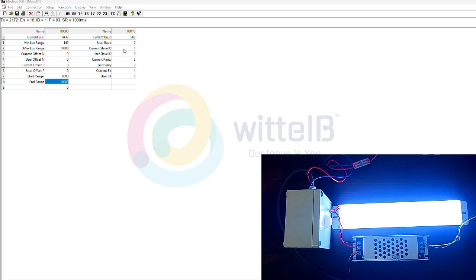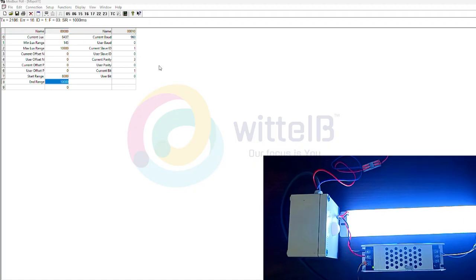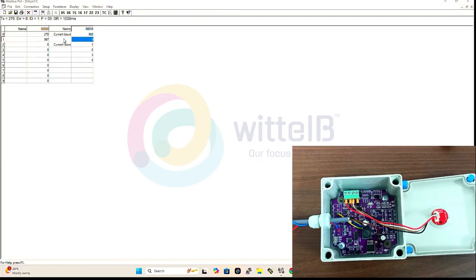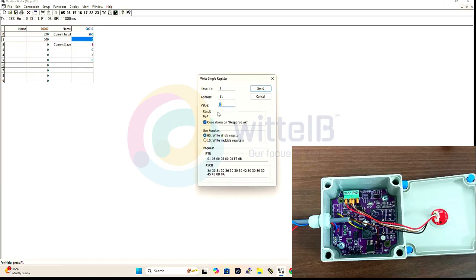Here you can also change the baud rate and the slave IDs. Whenever we change the baud rate and the slave IDs, we just need to set the jumper as single. Then we can change them, and the board will be configured with the new baud rate and slave ID. Now I will set the baud rate as 115200. Here the user can set the baud rate. Click on that and provide the baud rate as 11520, just provide 10 for the last digit, because it will be multiplied by 10. That means 115200. Now I will send the request.